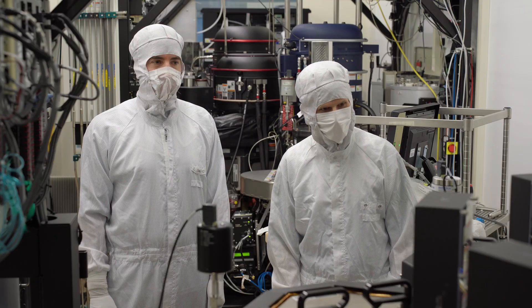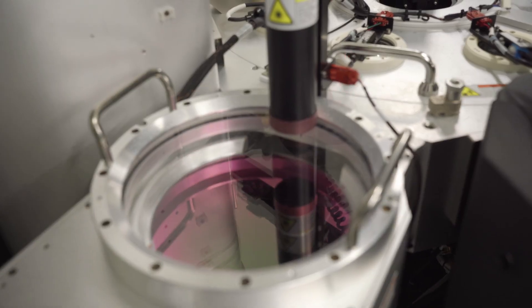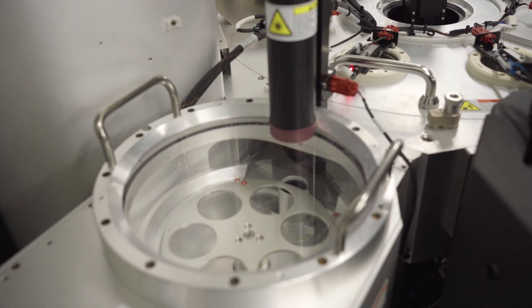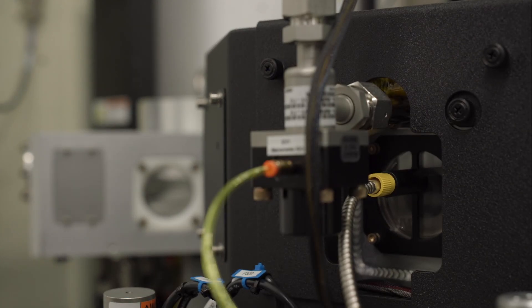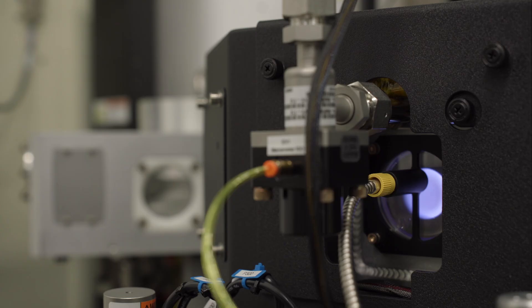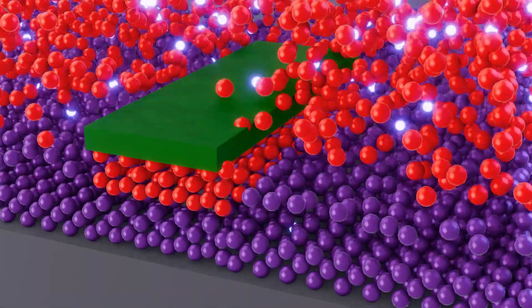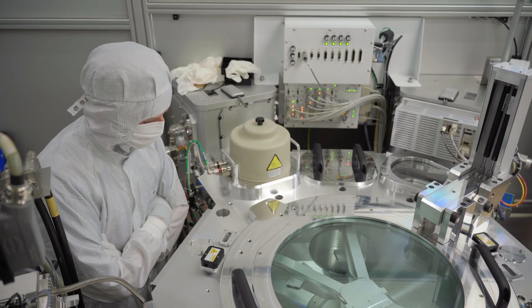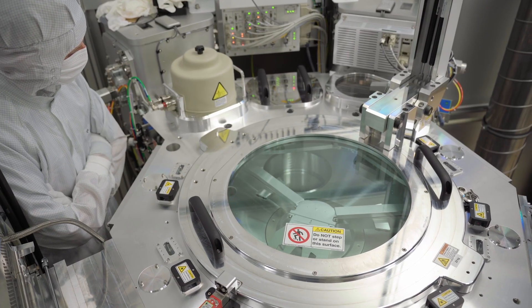This is a reactive ion etching tool. So here we are in the maintenance area of the clean room. In these kind of tools, we etch away material, as the name says. And we do this by creating a plasma above the wafer. We have reactive gases above the wafer. They get ionized in a plasma. And the way it's constructed is such that the plasma can react with the material that we want to etch away.